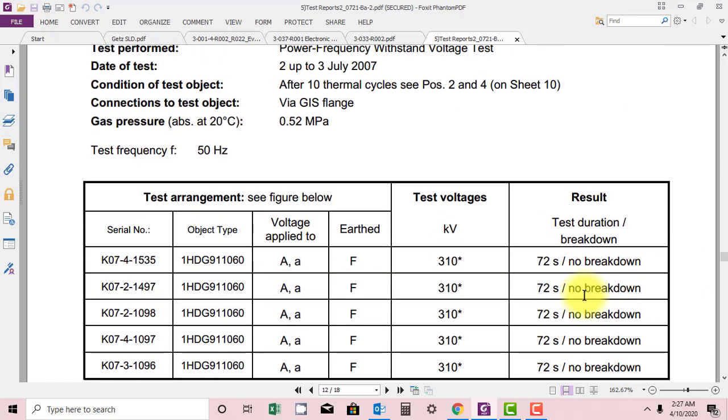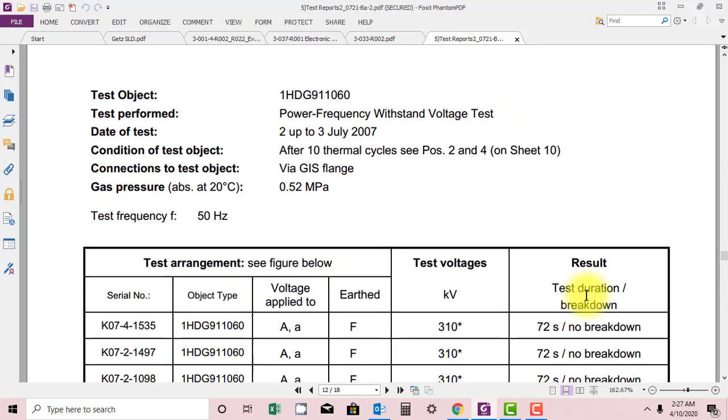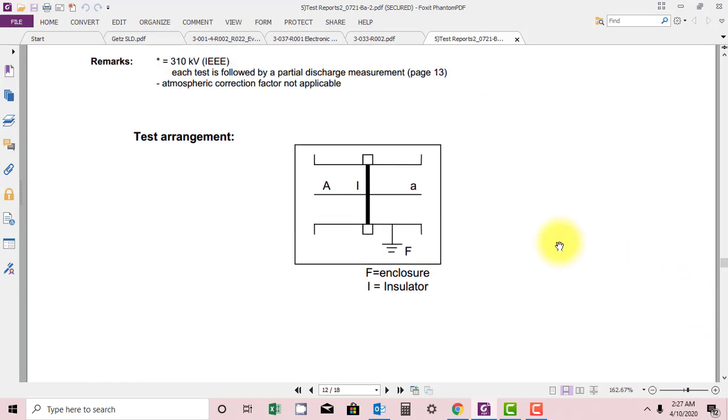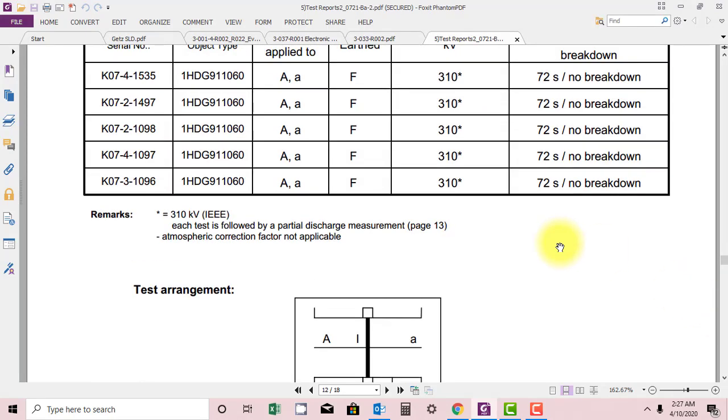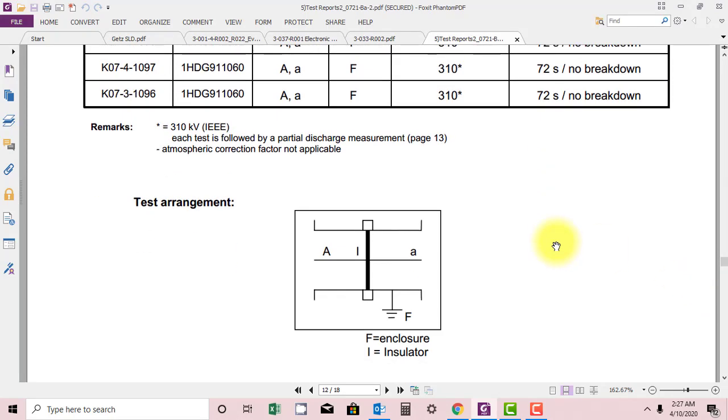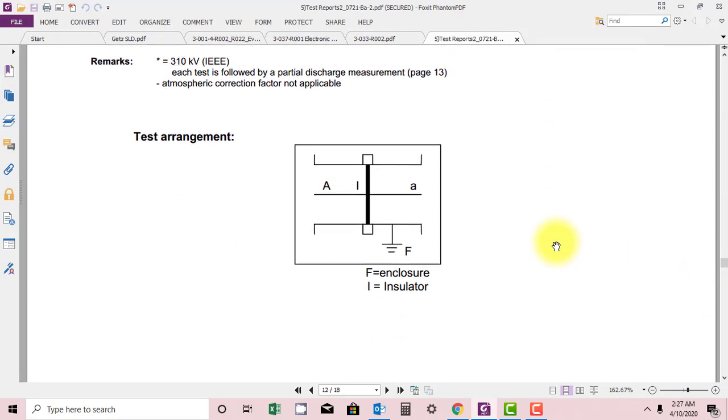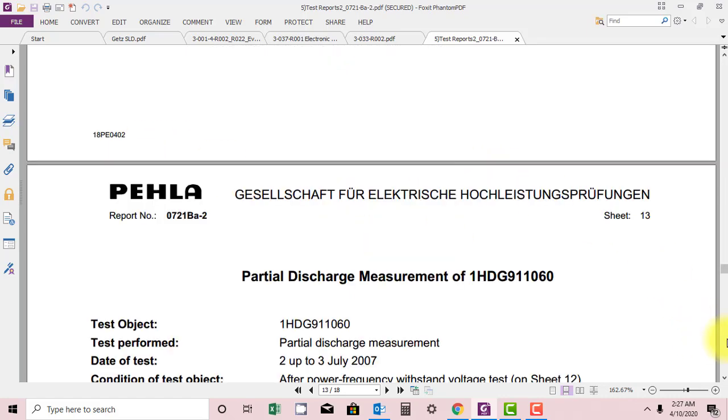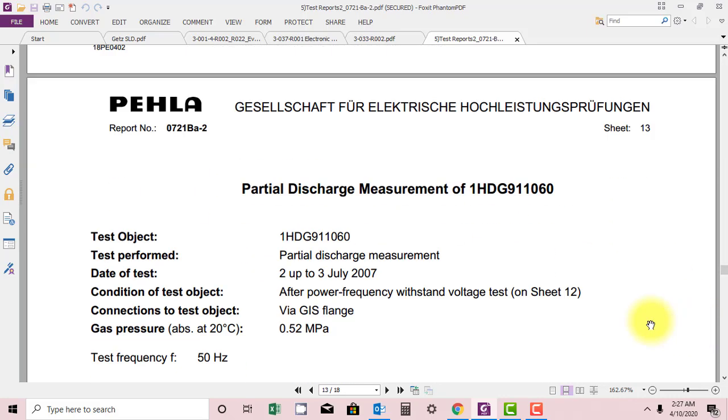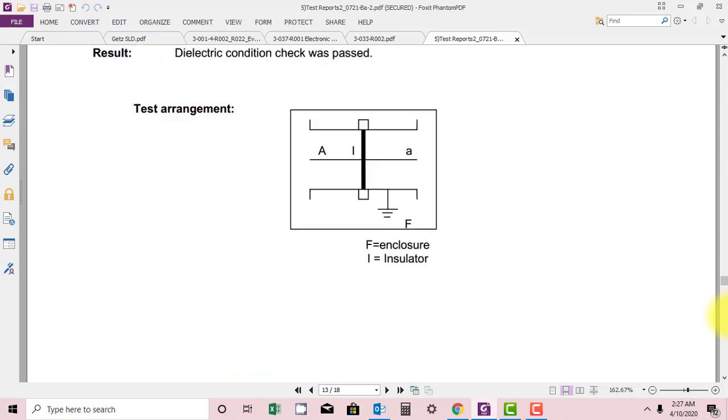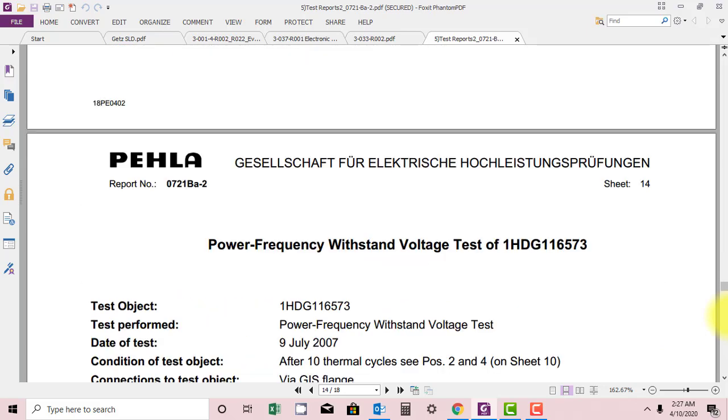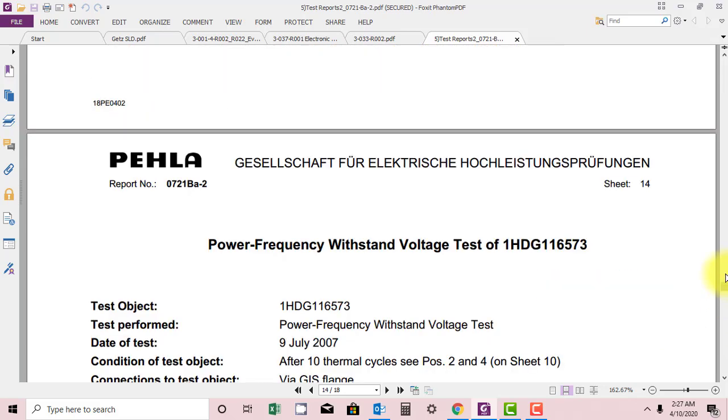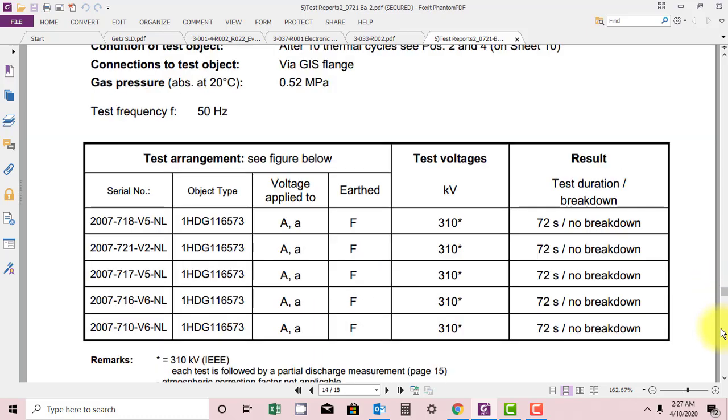They have done the dielectric test at power frequency up to 310 kV for 72 seconds. There should not be a breakdown. This is the arrangement: F is enclosure, I is insulator. So this is insulator they have grounded and applied voltage to the insulator, and they have done the partial discharge. And they have done power frequency withstand test voltage, again partial discharge.